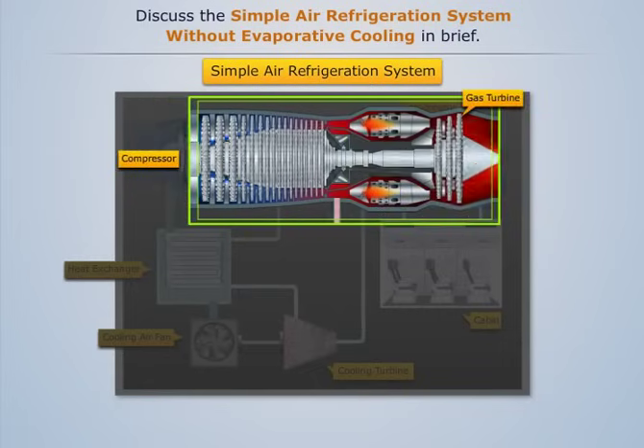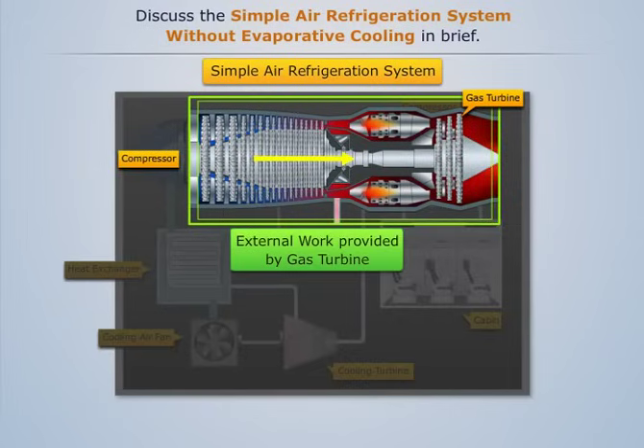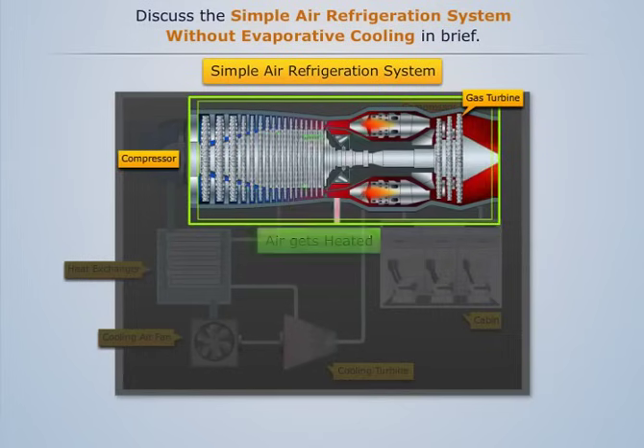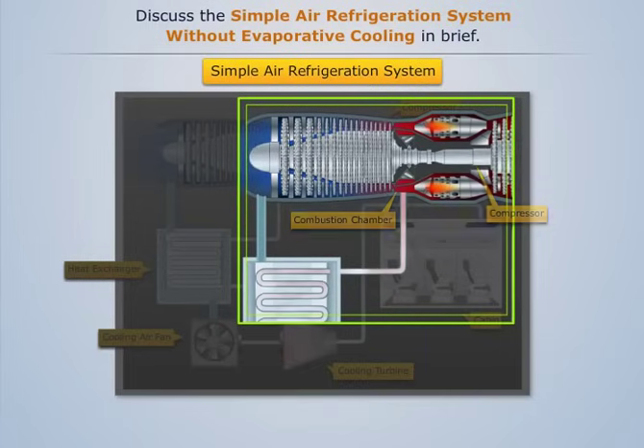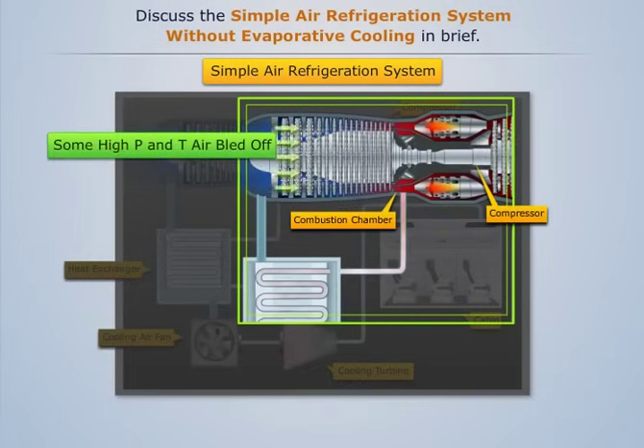The external work required by the compressor for this compression is provided by the gas turbine. In this process the air gets heated, and ideally this process is considered isentropic in nature. A small portion of this high pressure heated air is bled off from the main compressor, whereas the rest of the air is sent to the combustion chamber.